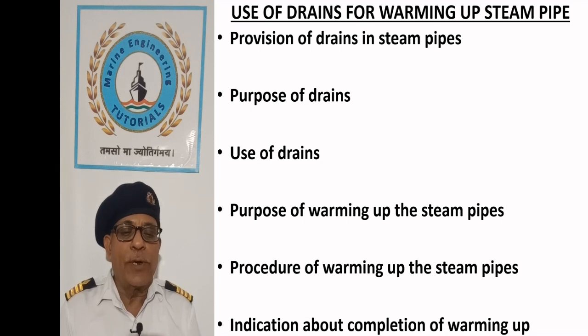Indication about completion of warming up. When the pipe has been sufficiently warmed up, as evident by the release of steam from all the drains, the drains can be closed. Steam stop valve is opened and warming up valve is closed.